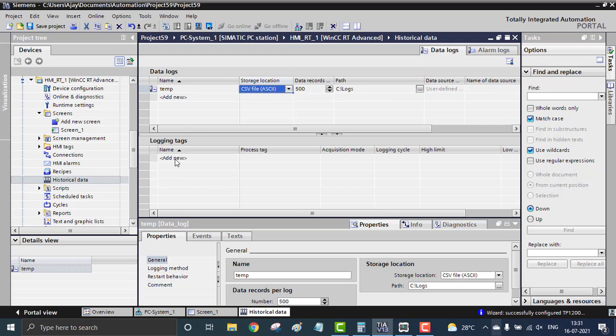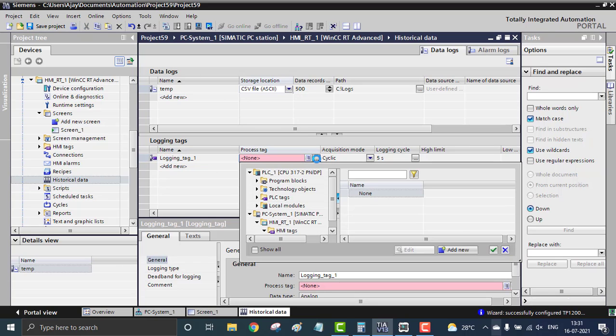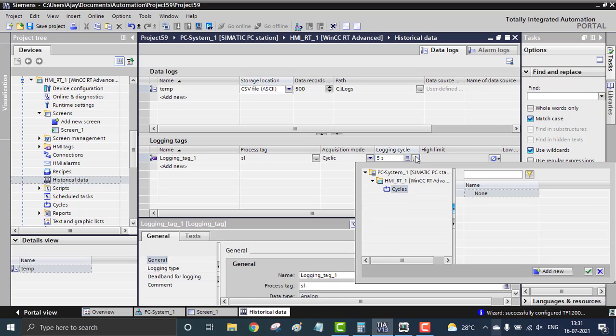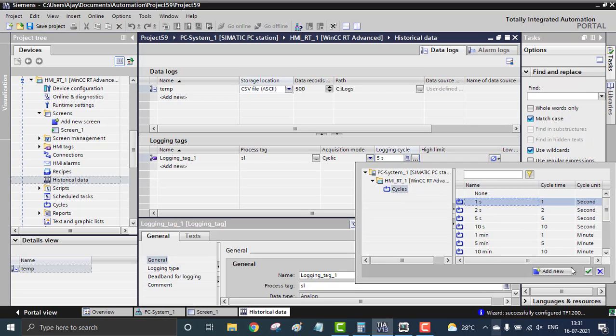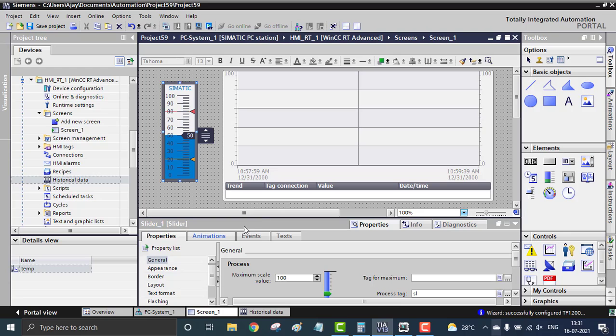Inside the temperature log I can add tags — I'm using one tag, which is 'sl'. The acquisition mode will be cyclic, with a logging cycle of one second for a better demo view. In normal use, we don't log every second for long-term data because that consumes too much storage — typically you'd log every few minutes or hours.